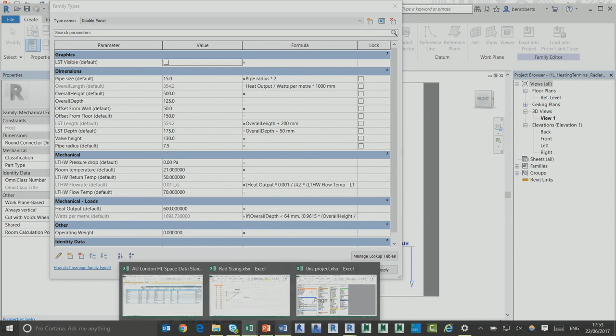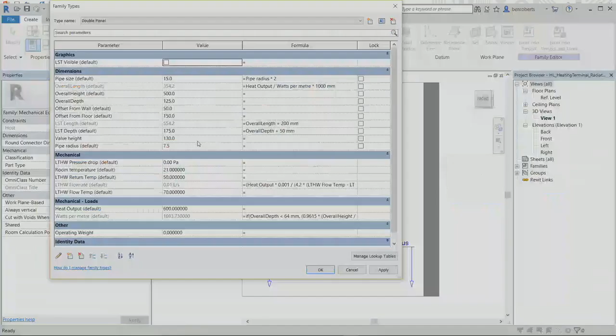The other thing I've done is add in some equations to size the length of the pipe based on the heat output, the height, and whether it's single or double panel. So I took some information from manufacturers and got these watts per meter values from manufacturers' data based on the different heights. I plotted a graph and copied the equation from Excel into here. Overall length is watts per meter, here, this one.